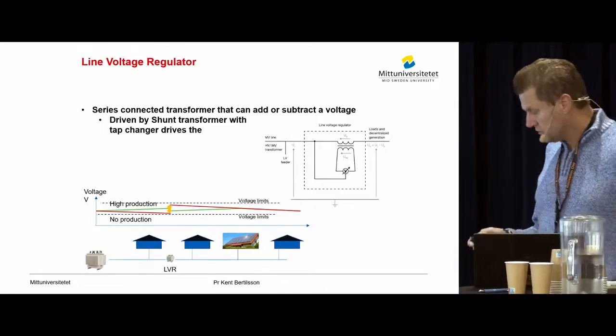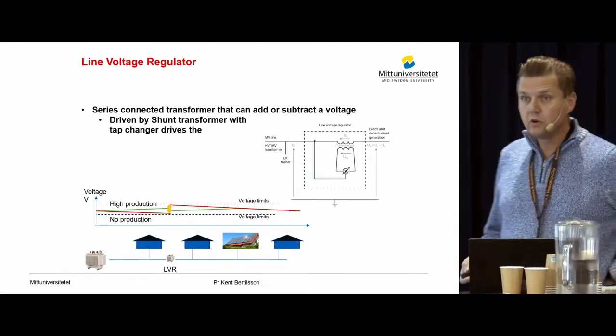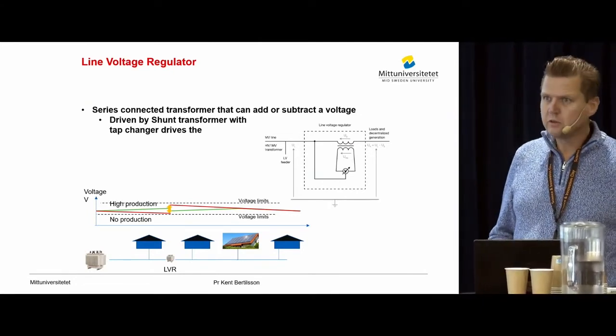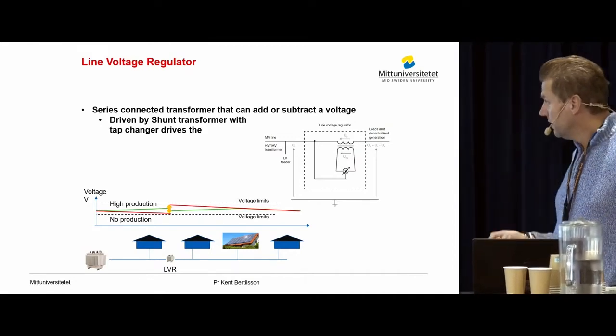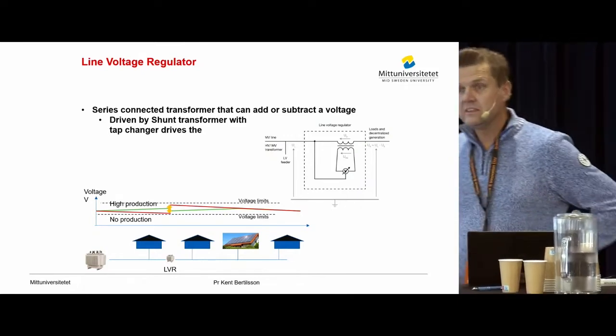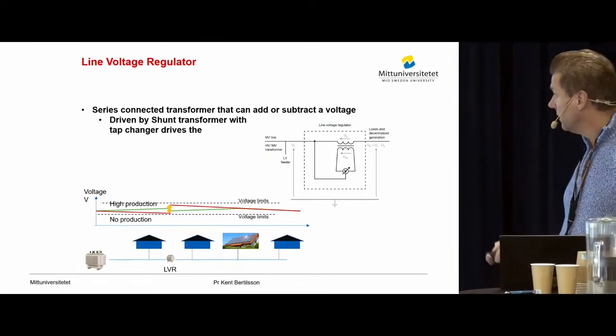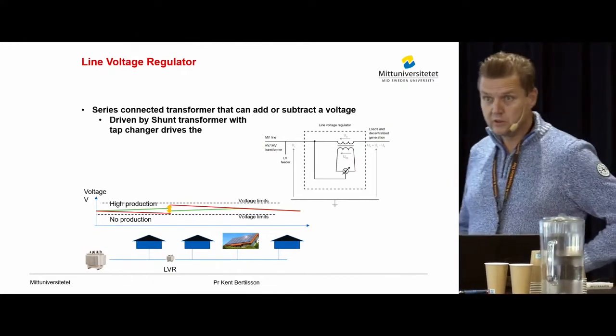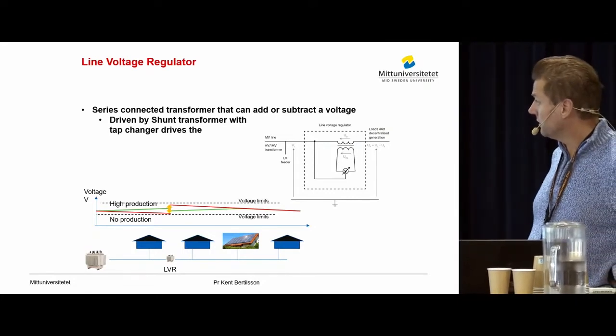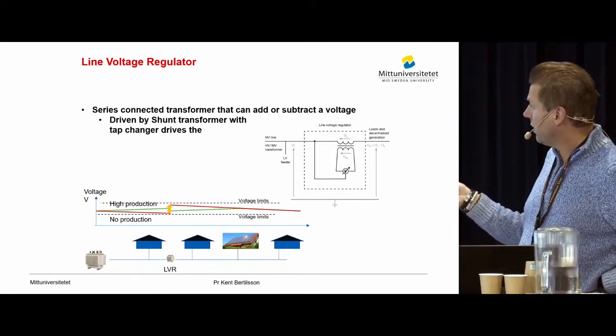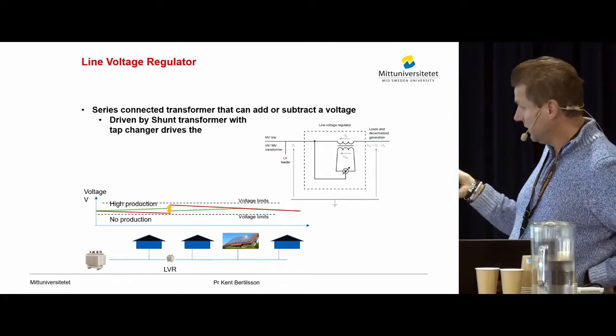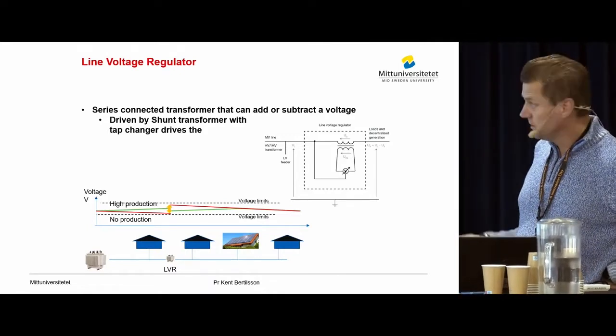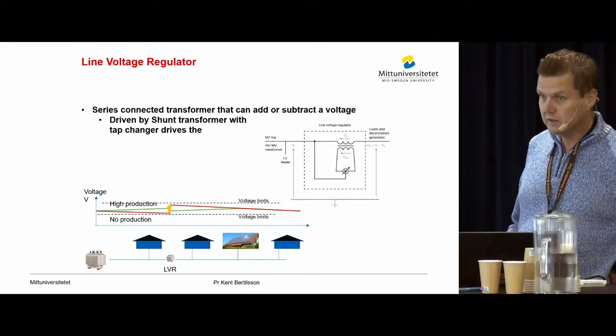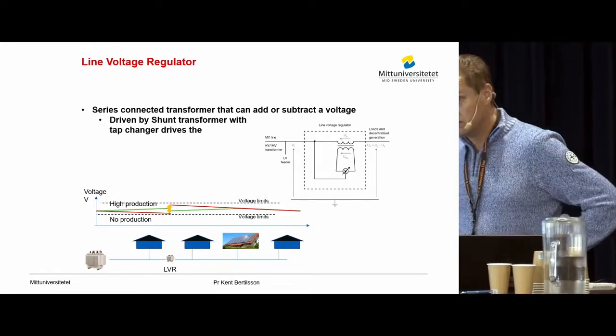Another interesting, closer, and perhaps more robust design is called an LVR, line voltage regulator. What that can do is have a small series transformer in the power grid. This series transformer can add or reduce delta V or delta voltage. You take power from the grid, feed it to the series transformer, and then add or reduce the voltage. That way you can handle it dynamically, and it can react much quicker. It's also closer to an iron nail solution, so it's more robust.